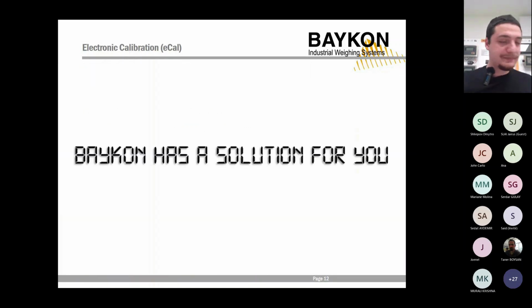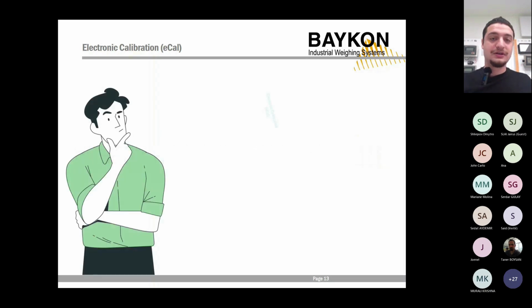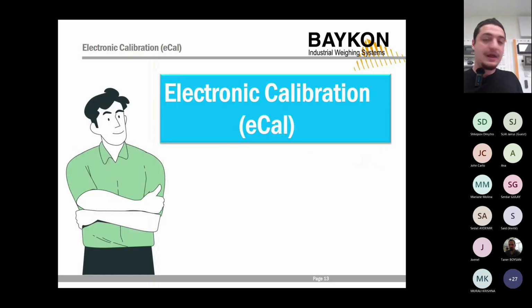Well, we have a solution, and we call that solution electronic calibration. At this point, from the feedback that we got from the field, we have chosen to integrate a technology called electronic calibration. It requires no logistics, it requires no labor, and in the worst case scenario it would take 5 minutes, and it requires no involvement of any type of weight of any range whatsoever, because this is fully electronic.